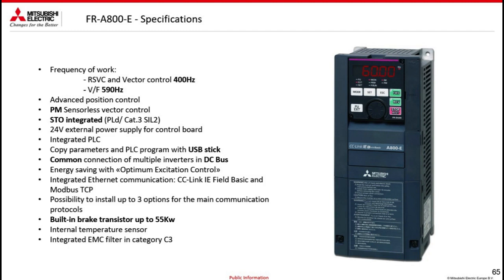It is the advanced position control. In fact, we can make real positions, mainly table positions. We can go to manage the PM motors. There is the STO integrated, the external 24-volt power supply, the PLC integrated, the possibility to copy the program parameters with the USB, the common connection of several inverters to a DC bus, and the optimum energy saving, not advanced like the other. In fact, the energy saving of the FRF 800 is better.